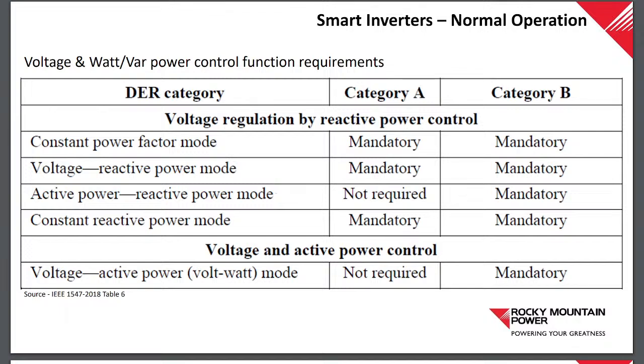One of the big changes we're seeing from the new updated standard is the normal operation for inverters. We're going from what was originally adopted in all of the existing net metering customers today, where we all have them set at the constant power factor mode, everything at unity, inverters set with no regulation, no active or passive regulation. Now it's defined into two categories: category A and category B. This is for the normal operation of your voltage and your watt and var power control.